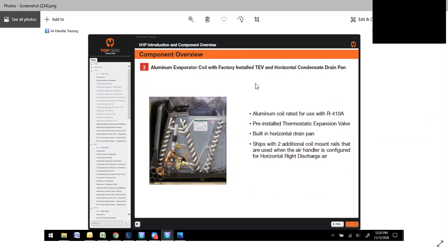This is the aluminum evaporator coil with the factory installed TXV, horizontal condensate drain pan included. These are aluminum coils, rated for 410A refrigerant. They have pre-installed thermostatic expansion valves. And if you look right here, as mentioned earlier, they're using the Chatleff connections on the expansion valves. There's no braze required. So if you do have to replace a thermostatic expansion valve, you basically have 3 bolt connections right here. That makes life a whole lot easier. It has a built-in horizontal drain pan and it ships with 2 additional coil rail mounts, so you can convert it to horizontal right.